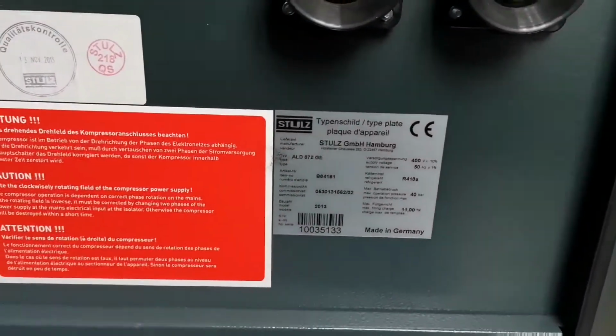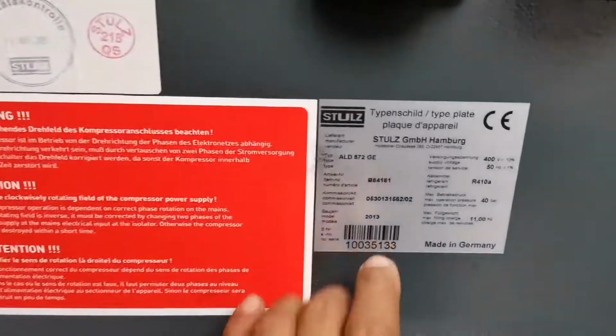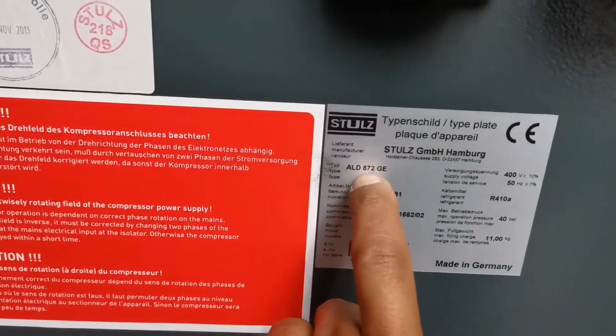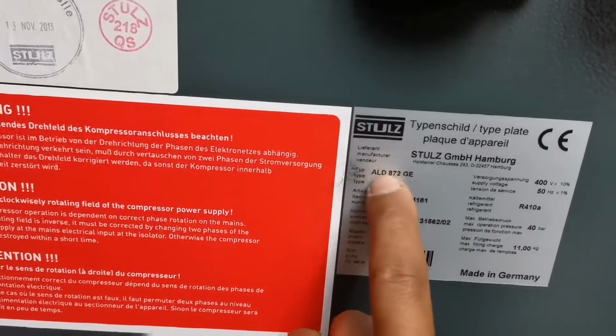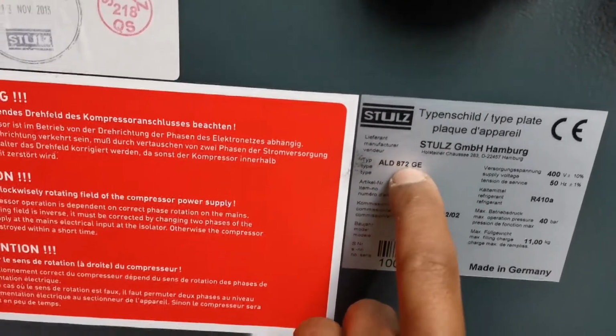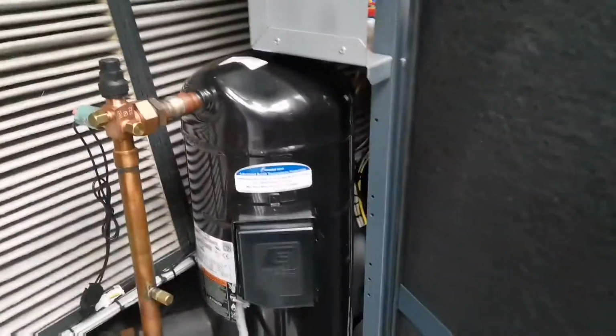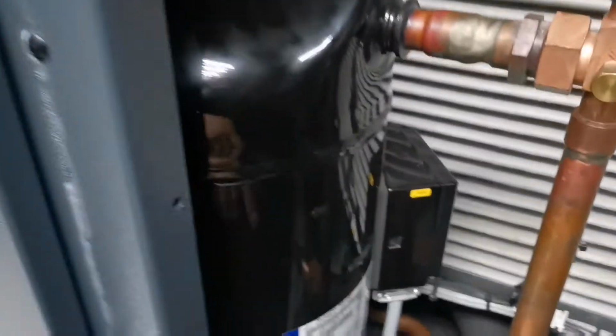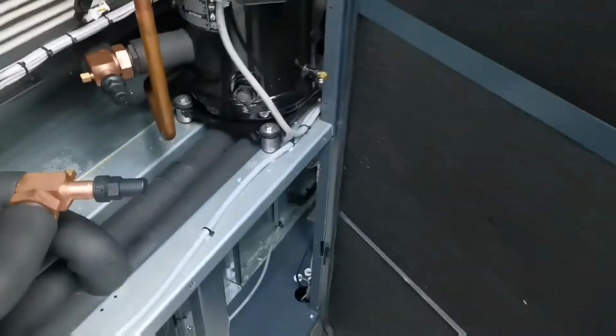This is an ALD872. So the first two digits there are for the kilowatt output, so it's 87 kilowatt, and the 2 stands for 2 circuits because we've got 2 compressor circuits. One coupling there, another one on this side. We've got our blower motors at the bottom. We've got 3 of them.